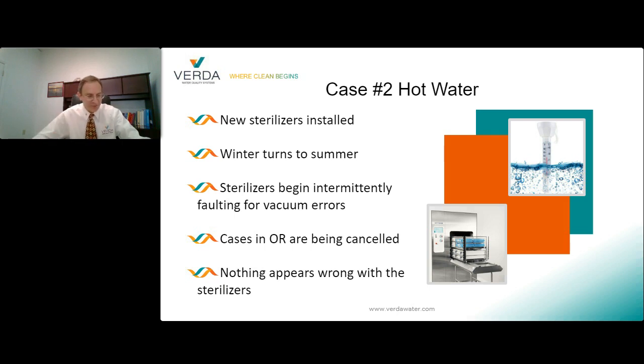These new sterilizers were designed with vacuum pumps that required facility water to act as a cooling medium. So during the winter months, when the water temperature was perfect, things were fine. Now, that second summer at the facility was a hot one. There were multiple heat waves, and the water supply came from the local river. And as the summer wore on, the municipal water temperature rose.